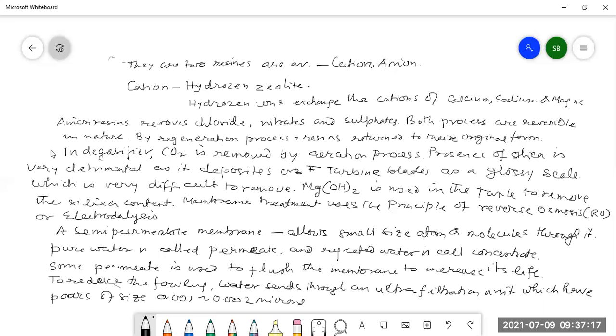Backwashing and flushing are alternately carried out to clean the membrane of residual salt a number of times. Now, if there is some stubborn fouling matter, chemicals like NaOCl, hydrochloric acid, and caustic soda are added to the backwash water, which is called a chemically enhanced backwash cycle.